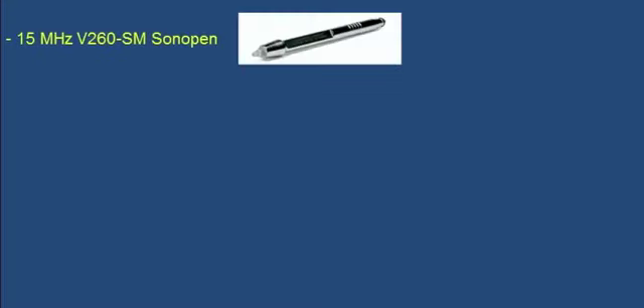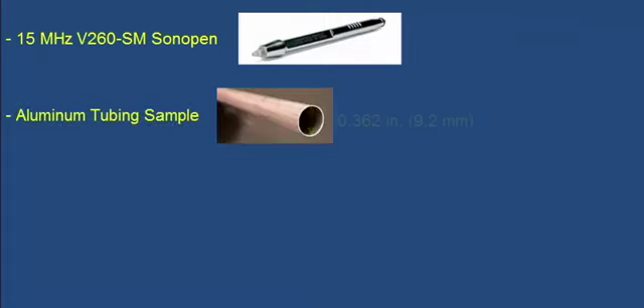In this demo, we will first show how to set up the 15 MHz V260-SM Sonopen delay line transducer to make measurements on a 0.362-inch or 9.2 mm diameter aluminum tubing sample with a wall thickness of 0.013 inches or about 1/3 of a millimeter.